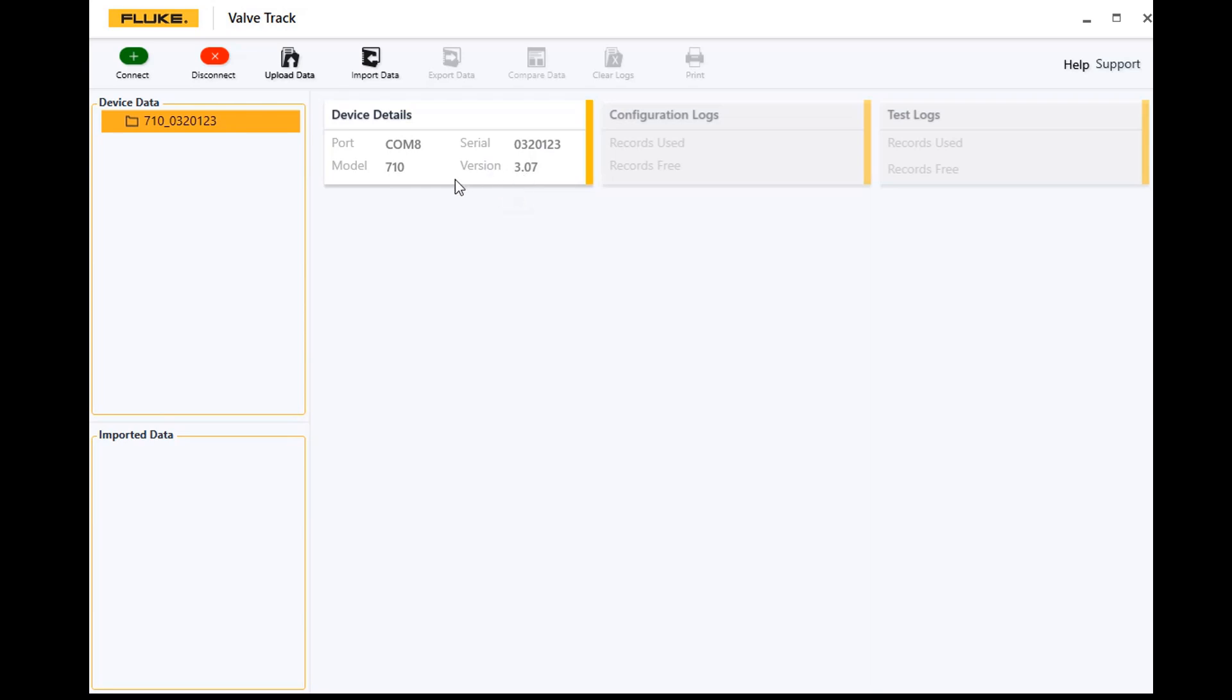At this point we can go ahead and go to upload data. From here we've got two choices: we can either upload config data, which is up to 20 different device configurations that you have saved in the 710, or you can upload test data, and those are test results from up to 100 test results by doing signature tests, speed tests, step tests, or bump tests.